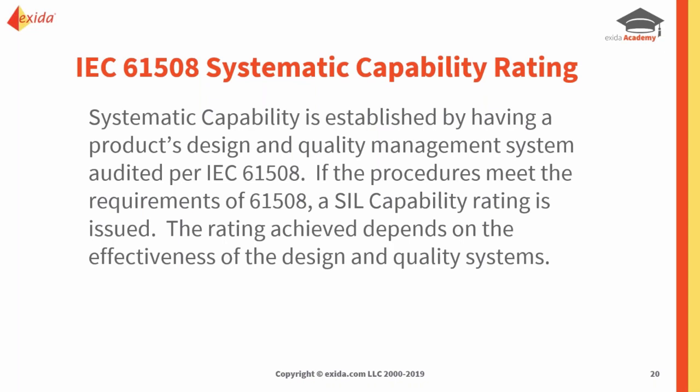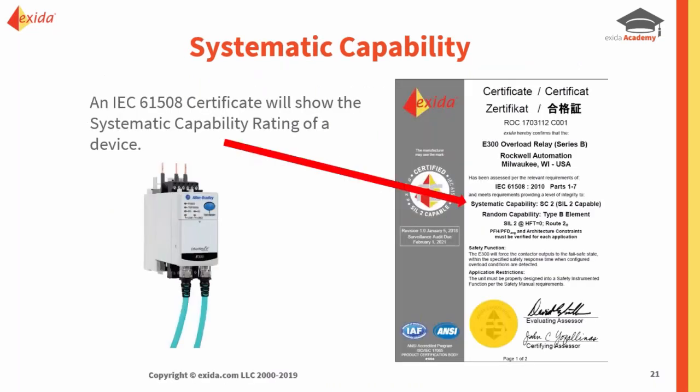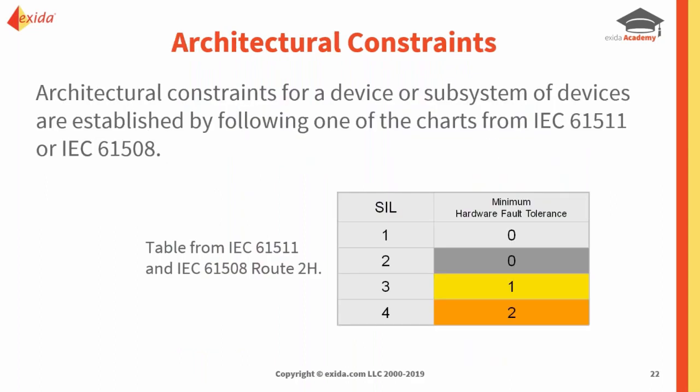The other way is the IEC 61508 systematic capability rating, which is established by having a quality management system audited per IEC 61508. If the QMS meets the requirements of the standard, a SIL rating is issued. The SIL rating achieved depends on the effectiveness of your quality management system — the more robust, the higher SIL rating you can achieve. Considerations include how you source part suppliers, how you make modifications, and how returns and recalls are handled. When a motor controller becomes certified, the systematic capability is shown on the product certificate. Without this certification, this barrier becomes very hard — the end user must go through prior use justification, which is a great deal of time and essentially money lost. It's a huge selling point for manufacturers if they can provide a certificate.